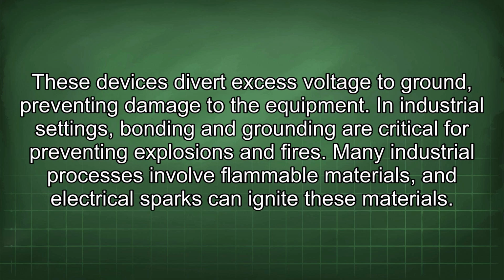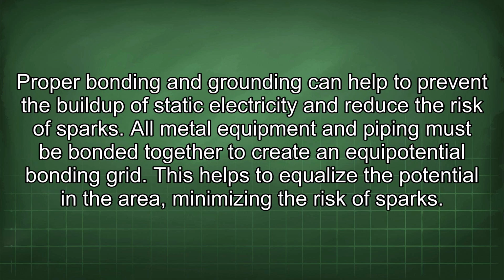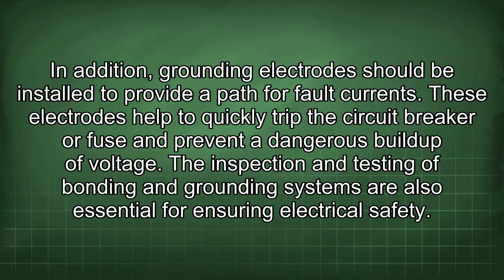In industrial settings, bonding and grounding are critical for preventing explosions and fires. Many industrial processes involve flammable materials, and electrical sparks can ignite these materials. Proper bonding and grounding can help to prevent the buildup of static electricity and reduce the risk of sparks. All metal equipment and piping must be bonded together to create an equipotential bonding grid. This helps to equalize the potential in the area, minimizing the risk of sparks. In addition, grounding electrodes should be installed to provide a path for fault currents. These electrodes help to quickly trip the circuit breaker or fuse and prevent a dangerous buildup of voltage.